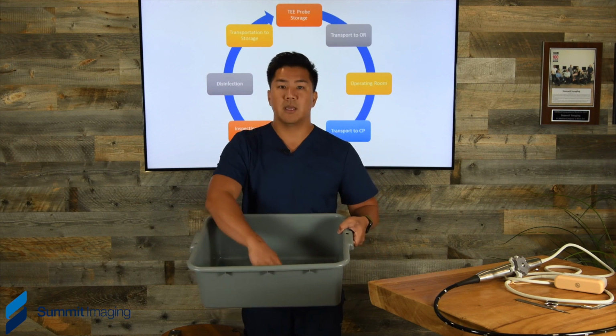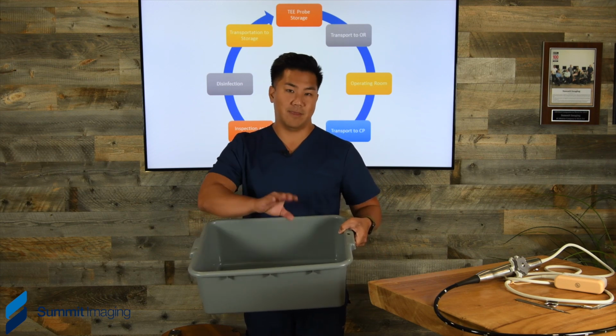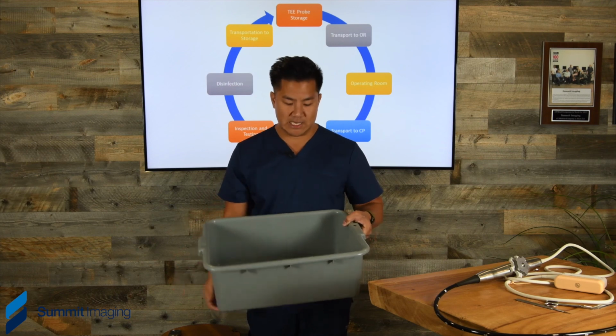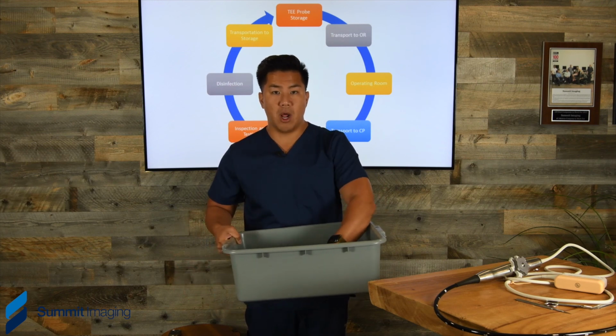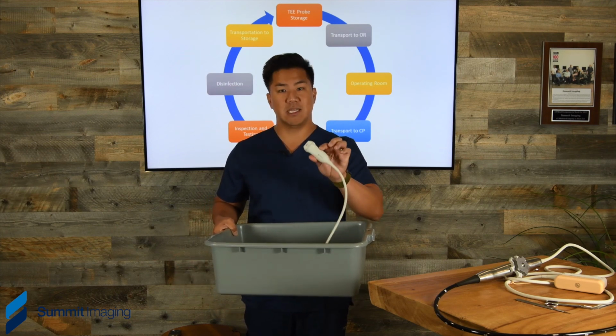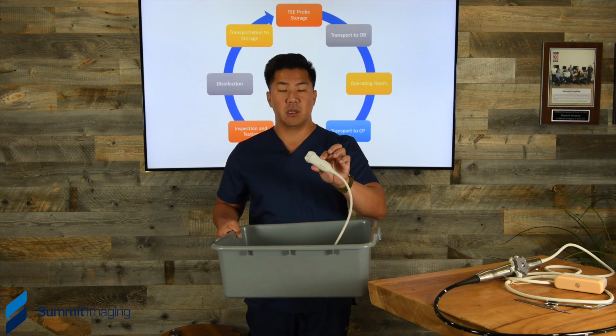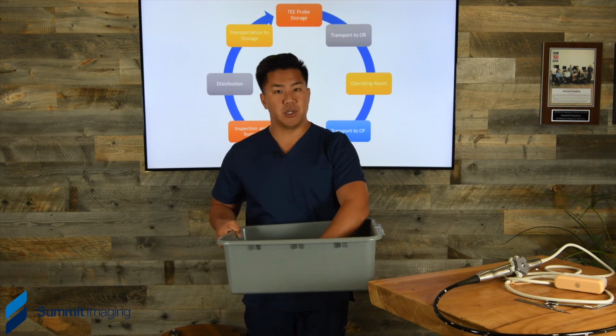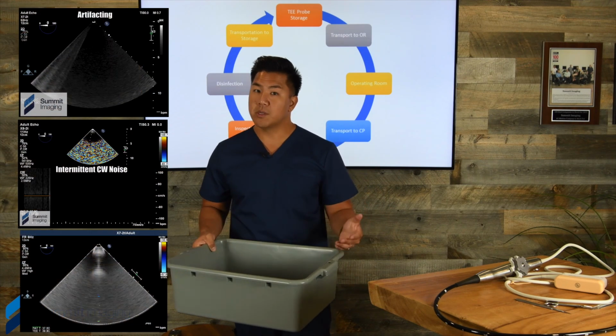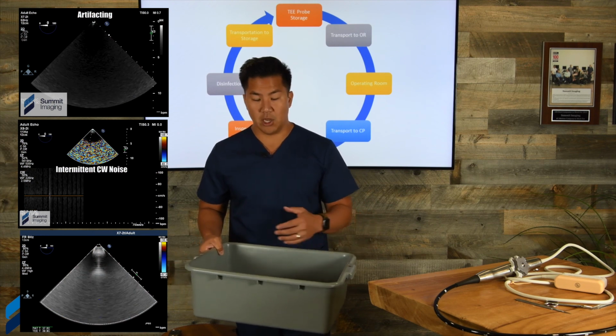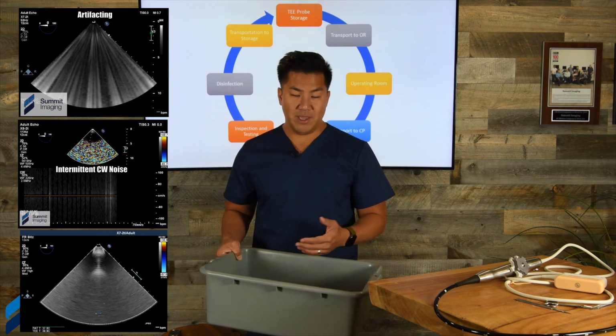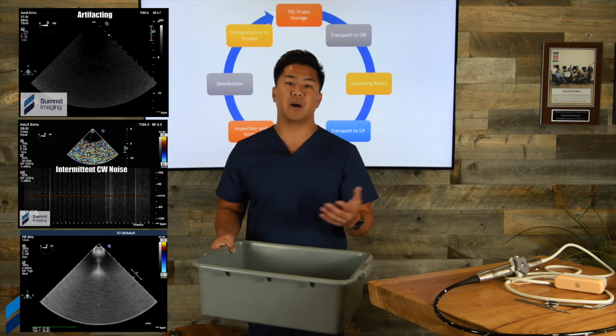The connector hits that crystal, and at that point, that impact is enough to disrupt the microelectronics inside of this transducer to cause imaging issues. It could cause color noise, it could cause CW noise, it could cause dropouts in your image. It could even cause the probe to malfunction and not even turn on anymore.